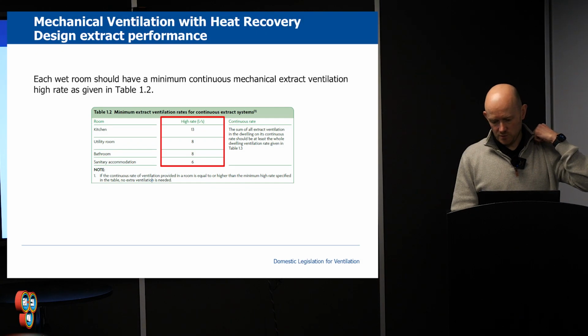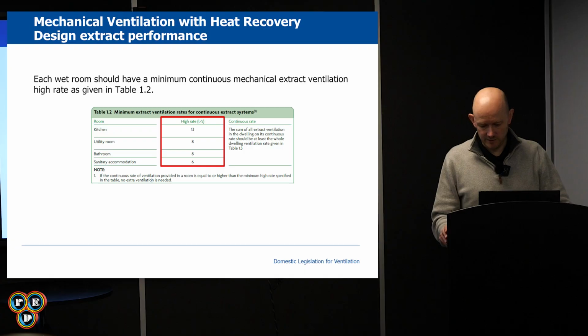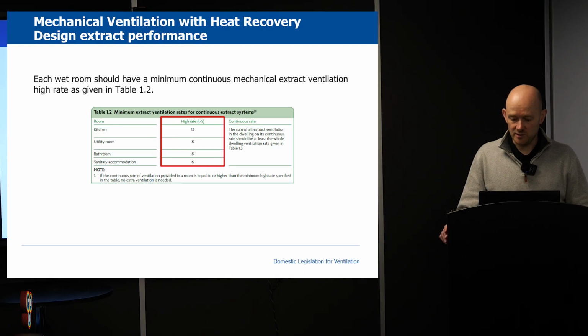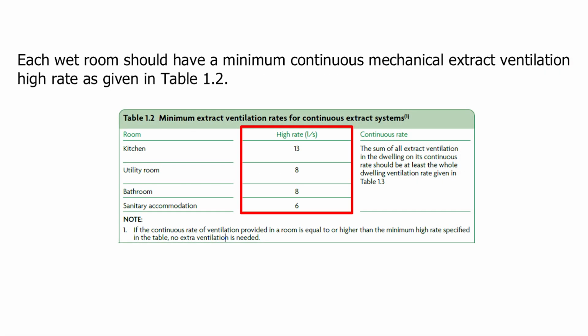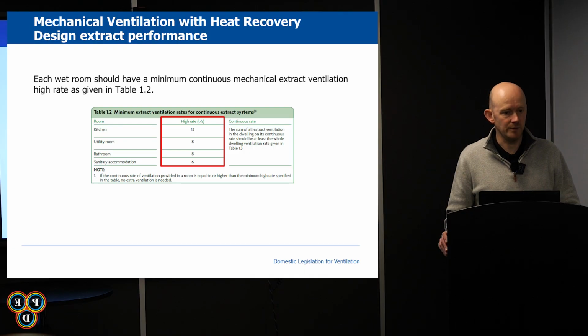For MVHR systems, we look at a high boost rate and also the continuous rate, just as we do with the MEV and DMEV systems. The minimum high rate is again defined in litres a second for each of the wet rooms: kitchen 13 litres, utility 8, bathroom 8, sanitary 6. It's very rare to get flow rates as low as that. It's only going to be a 100 square metre house. Anything 120, 150 square metre house, you'll probably find that we will be beyond those numbers. We'll be higher than that.